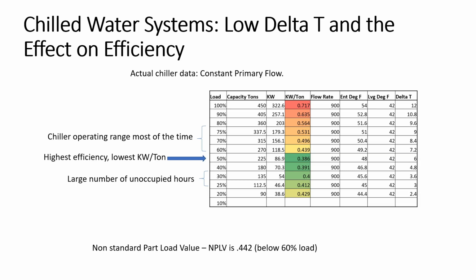And then we get into this term of non-standard part load value. That's the rating that tries to compare the efficiency of the chiller based on a non-standard load. It's this varying load. And so we use this number a lot to try to figure out if this is the most efficient operation or not. In this case, it's 0.442 on this machine, which is actually below its 60% load. So if you could maintain that 60% load or at that 0.442, that would be good, because that would be kind of an average on its non-standard part load value.